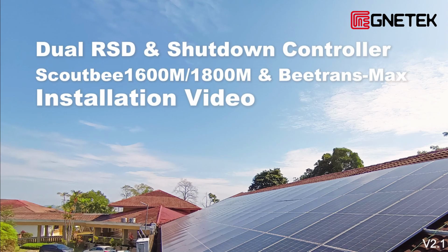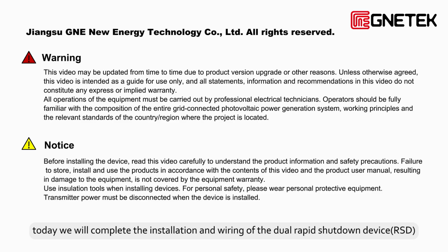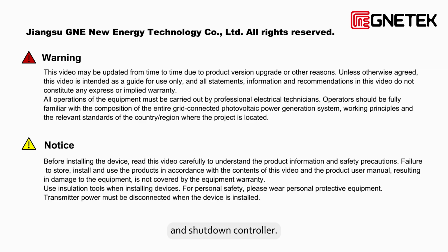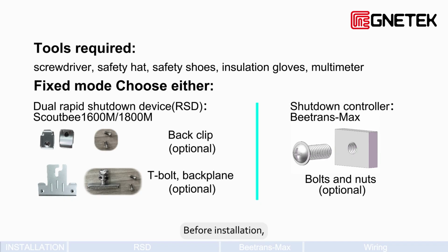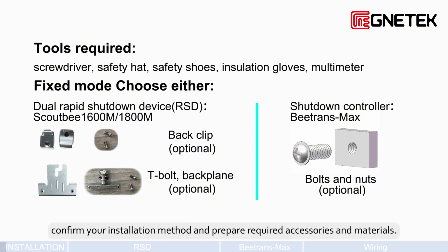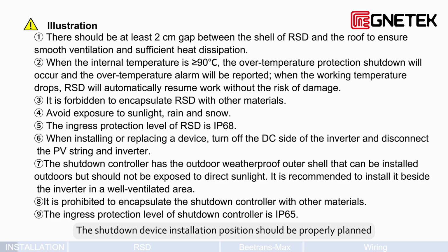Hello everyone. Today we will complete the installation and wiring of the Dual Rapid Shutdown Device, RSD, and Shutdown Controller. Before installation, confirm your installation method and prepare required accessories and materials. The shutdown device installation position should be properly planned to ensure that the cables between the shutdown device and PV modules and between adjacent shutdown devices can be properly connected.